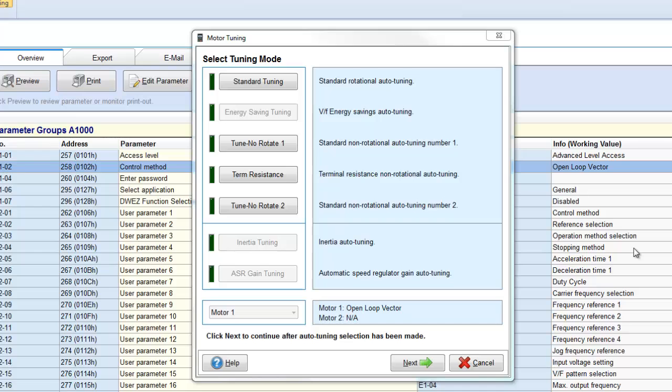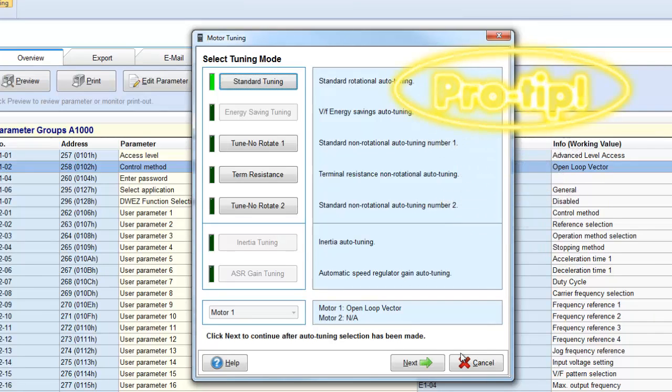Select which auto-tuning method you want to perform. Some auto-tuning methods will rotate the motor and others are stationary and will not rotate the motor. Be aware of which auto-tuning method rotates the motor before just clicking through it.